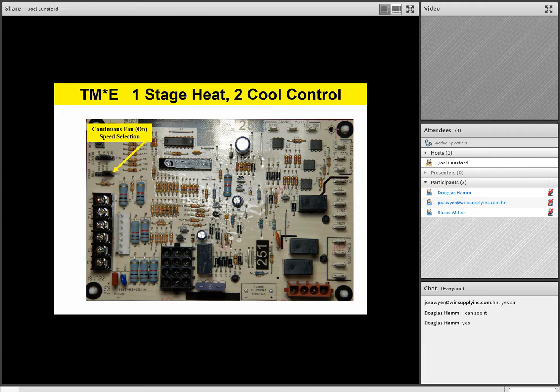So the selections are G, high cool, heat, and low cool. If you look on the upper part of the right-hand side of the board, you'll see there are different speed taps going to the motor. So based on where that jumper selection is, if the homeowner calls for continuous fan and they just want the fan to run all the time, the speed with which it'll run will be based on that jumper where it says fan speed. Any questions or comments on that? So again, this is a continuous fan speed selection.